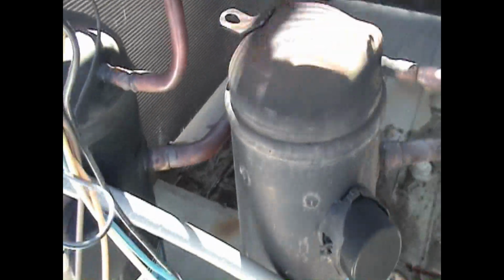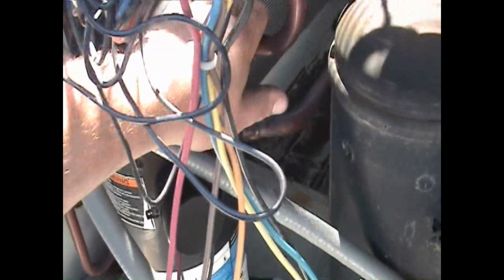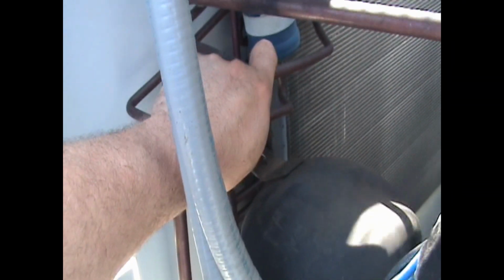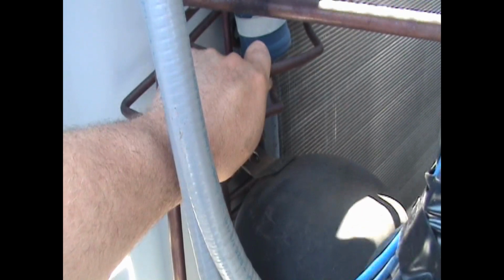This is the compressor that was running, nice and cold coming back, we're pulling some heat. This is the compressor that was not running, hot as hell. Same temperature coming back as that one, we're definitely pulling heat. These liquid lines here, nice and lukewarm.